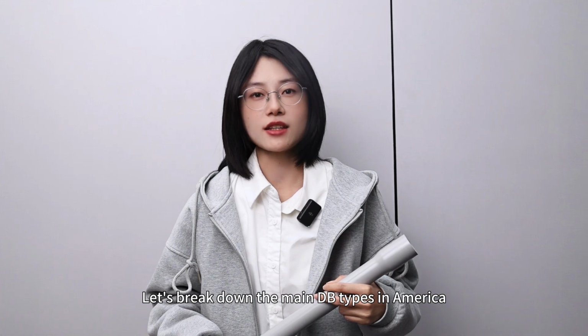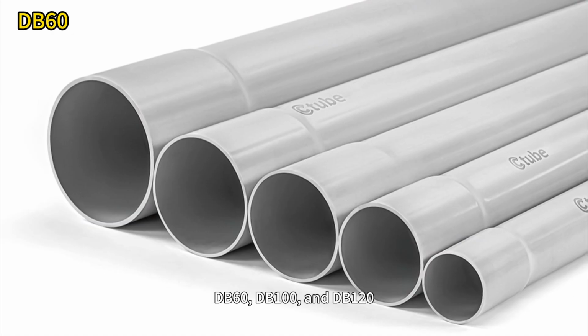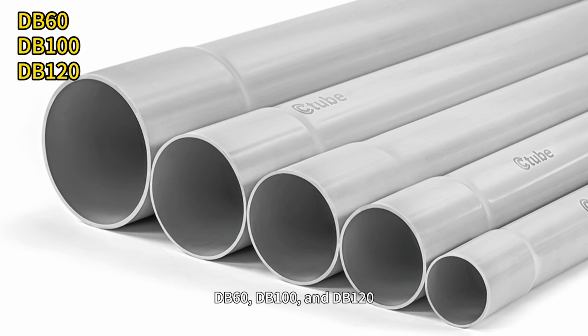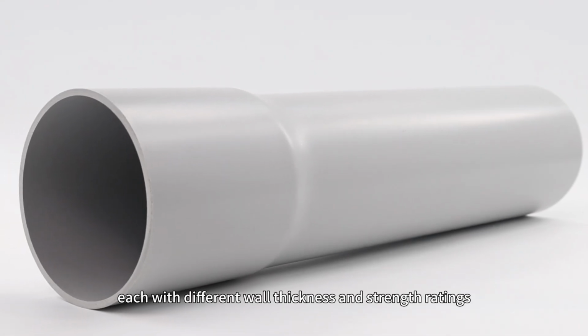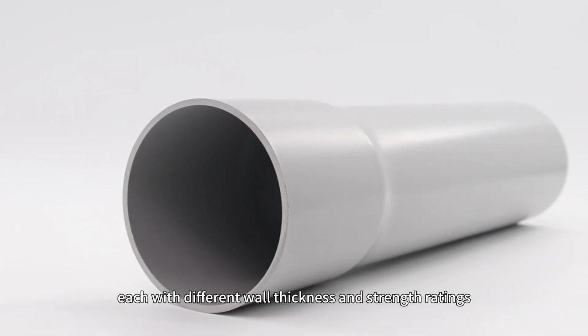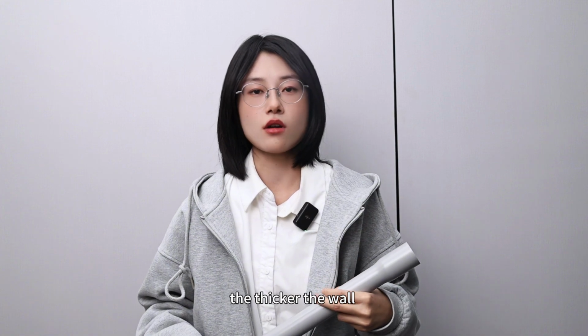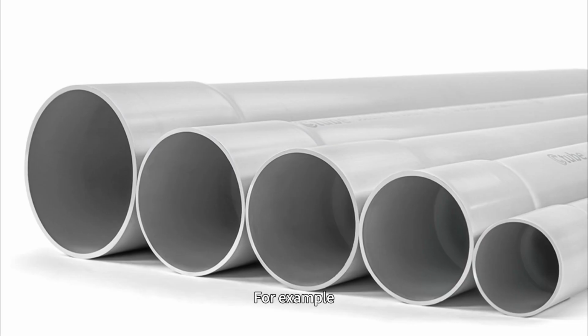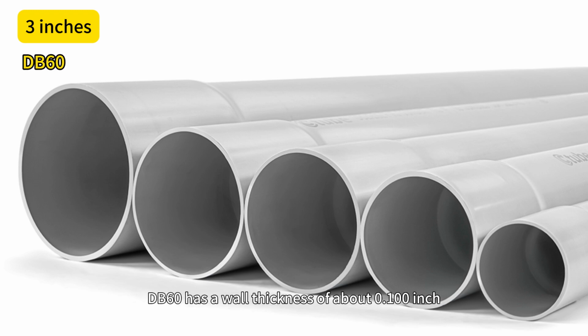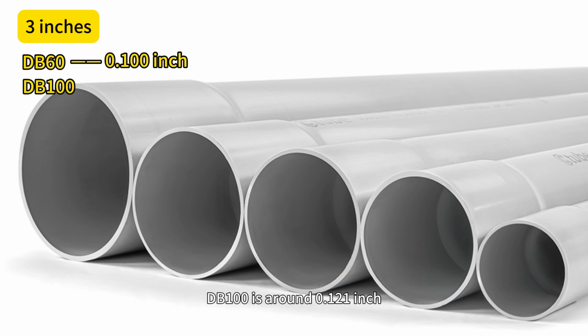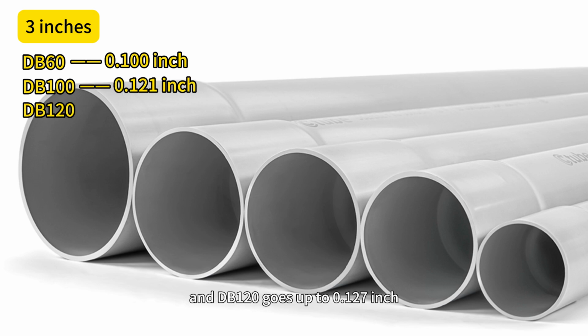Let's break down the main DB types in America. DB60, DB100, and DB120, each with different wall thickness and strength ratings. The higher the number, the thicker the wall, and the more durable the conduit. For example, at 3 inches, DB60 has a wall thickness of about 0.1 inch, DB100 is around 0.121 inch, and DB120 goes up to 0.127 inch.